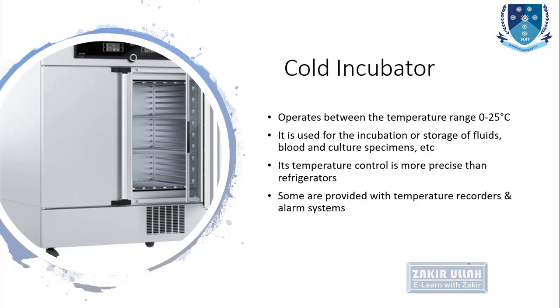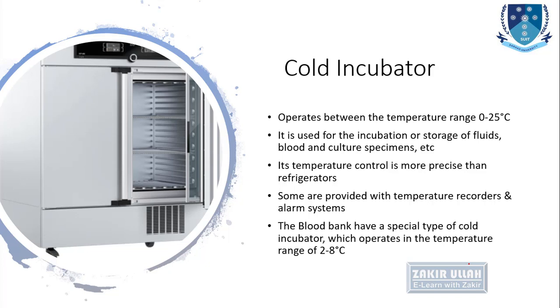Some designs are provided with temperature recorders and an alarm system, so if they cross the limits of the required temperature the alarm rings, and they also record the temperature throughout the day and week, so that if there is any deviation we can check the temperature afterwards. The blood bank has a special type of cold incubator which operates at 2 to 8 degrees centigrade to maintain the internal temperature of the blood bags.